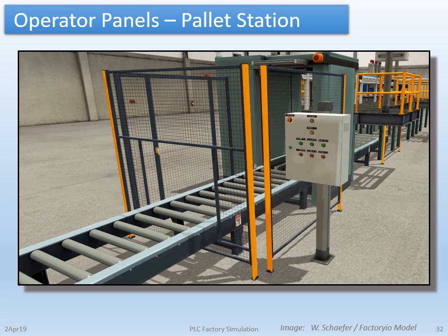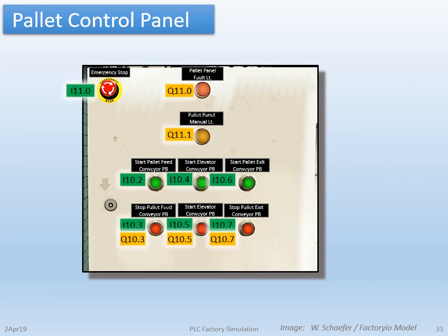Finally, the pallet entry and exit area has its own push button panel located at the bottom corner of the elevator where it is better to see the pallet conveyors. Manual panels within line of sight of the equipment to be controlled is a very important concept. Similarly, the pallet panel has manual indicators plus the appropriate buttons to start and stop the conveyors, and indicators to show the status of the conveyor motors.